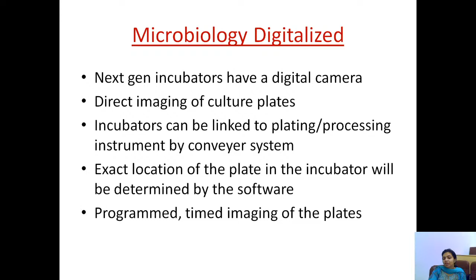So these next generation incubators have a digital camera in them. There can be direct imaging of the culture plates. Incubators can be linked to the plating processing instrument by a conveyor system, and the exact location of the plate in the incubator will be determined by the software. There is programmed and timed imaging of the plates. Whenever there is some growth, the camera will capture the image, it will beep and just tell that this plate has growth. All of these images are stored in the system. Images can be analyzed by the technologist on the computer screen, can be magnified, and can be observed under different lighting conditions. Better and earlier appreciation of the growth is possible due to the better optics.